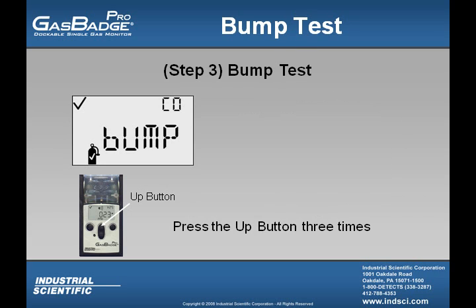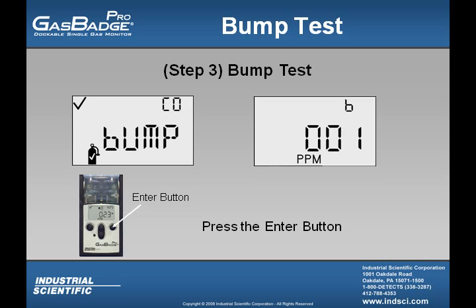With the bump test feature enabled, the user must press the up button 3 times. The user will then see the word bump flashing, letting the user know they are now in the bump test mode. Once the word bump is flashing, the user must now press the enter button, and they will see the numbers start to flash, as well as the letter B show up on their screen, just like the display on the right.